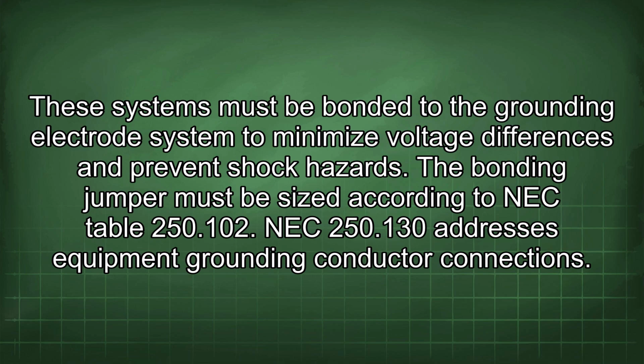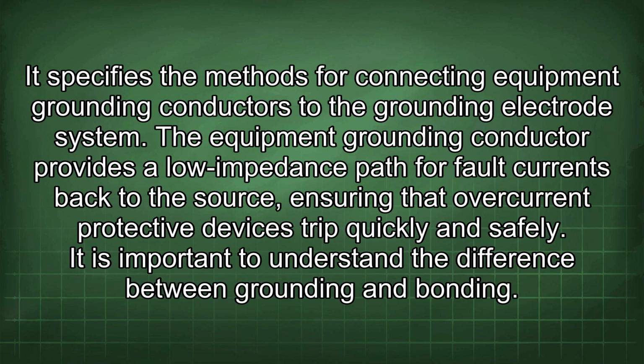NEC 250.130 addresses equipment grounding conductor connections. It specifies the methods for connecting equipment grounding conductors to the grounding electrode system. The equipment grounding conductor provides a low impedance path for fault currents back to the source, ensuring that overcurrent protective devices trip quickly and safely.